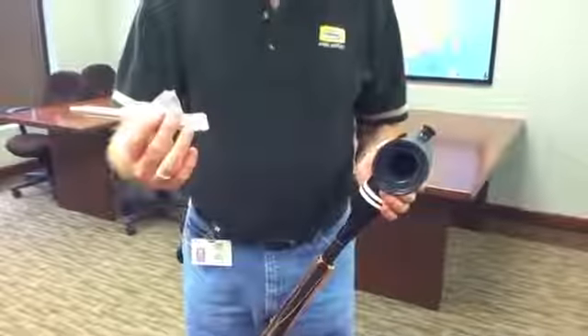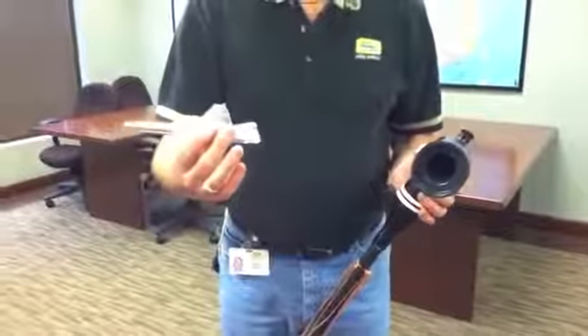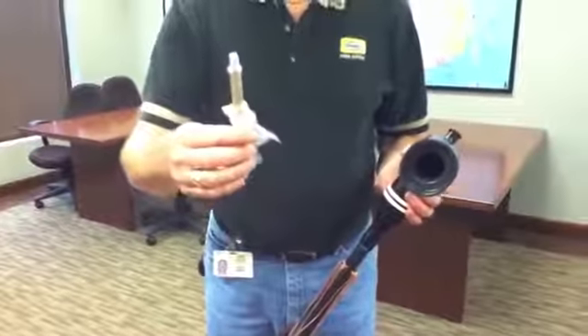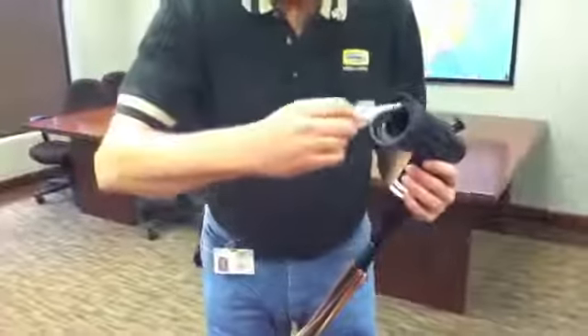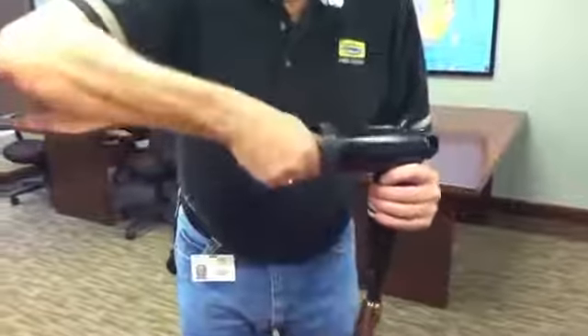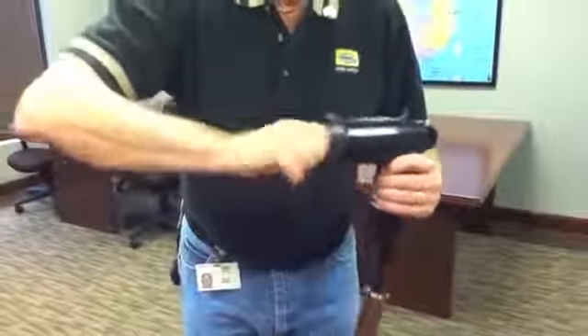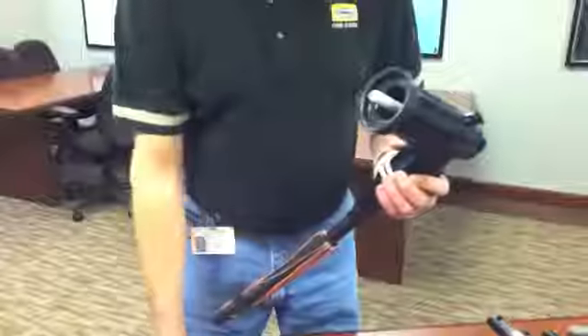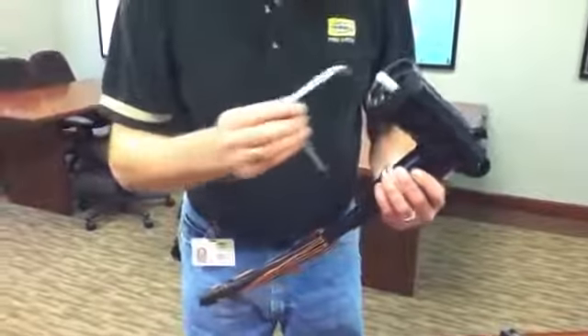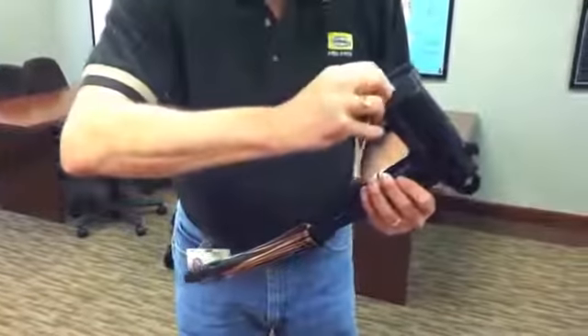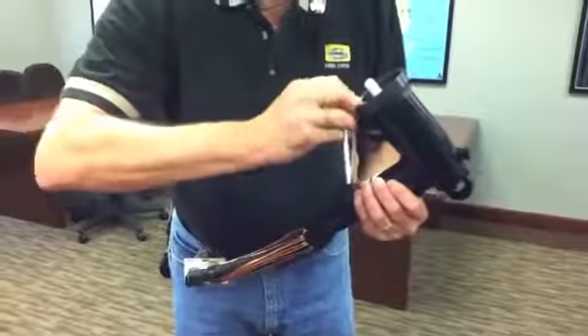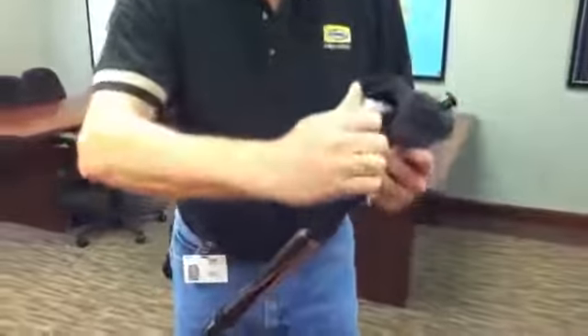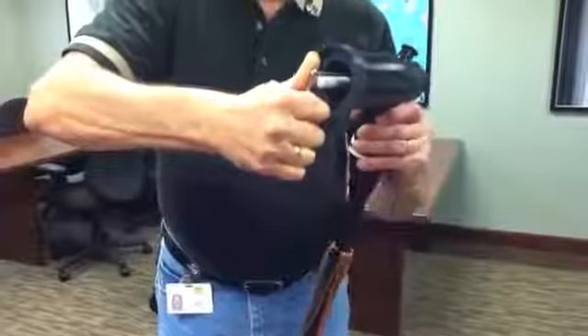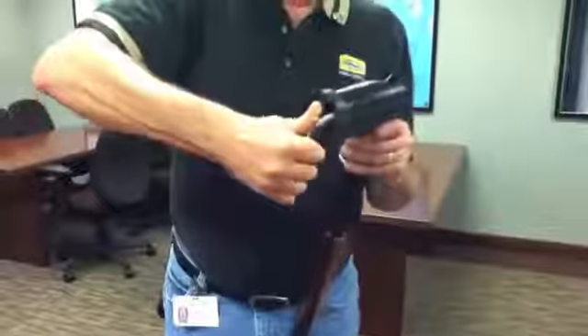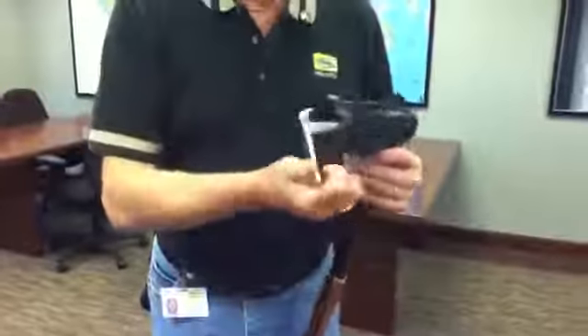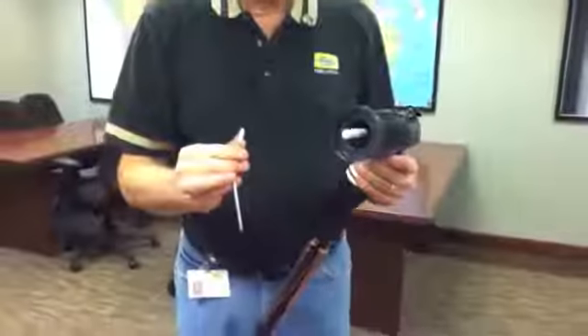In order to keep the follower material clean, you may want to just remove the plastic from the base. Hand tighten it in approximately 8 turns. Then, using the pin wrench supplied or an approved tool, insert and twist the wrench until the wrench yields, signifying that proper torque has been applied to the probe.